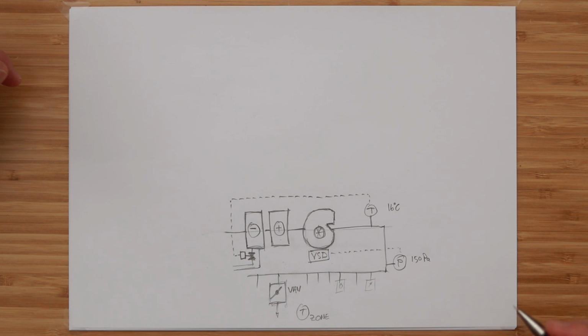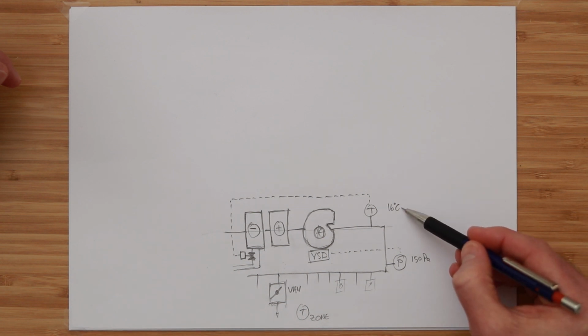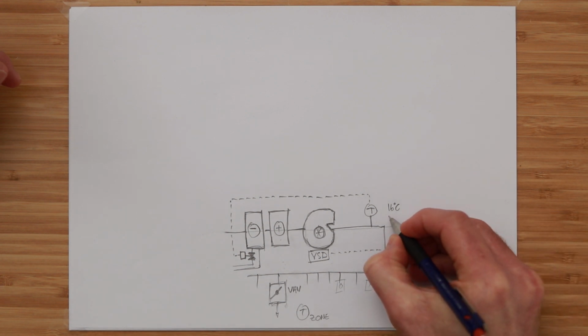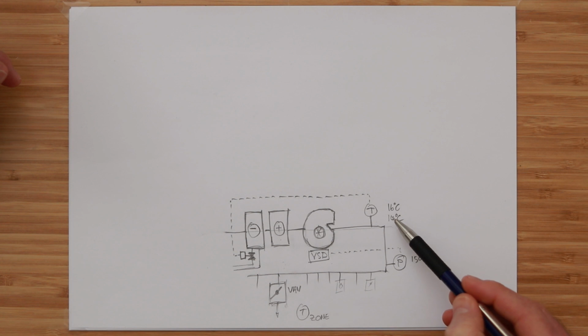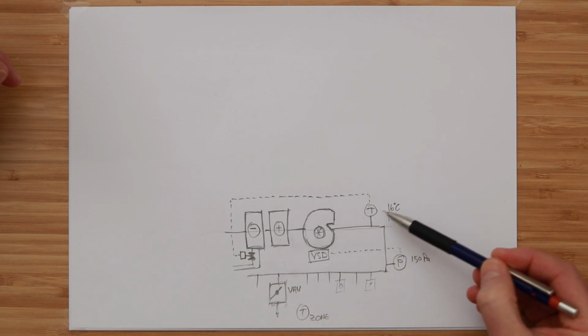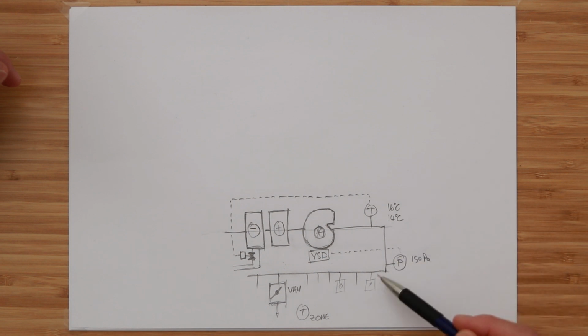But where it gets interesting is that with the supply air temperature set point, if you drop the supply air temperature set point just slightly, what happens is the cooling valve opens a little bit and colder air goes through the air handling unit, down the riser, and that cooler air goes through all the VAV boxes, and that cooler air drifts onto the temperature sensors, and the temperature starts to read slightly lower. It just drops 0.1 degrees Celsius, 0.2 degrees Celsius, 0.3 degrees Celsius. And as that temperature starts to slightly drop from the cooler supply air, all the VAV dampers start to slightly back off a little.